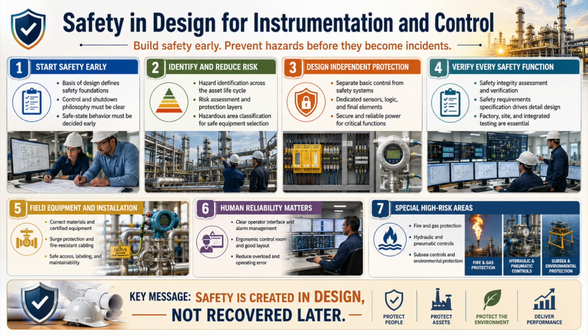A failed safety sensor is not a minor maintenance notification. It represents the loss of part of a protective layer. It must generate a clear alarm at a continuously attended location. Bypasses and maintenance overrides must be visible, controlled, time-limited, and alarmed. Emergency shutdown switches must be protected against accidental operation, clearly identified and easy to operate under stress.